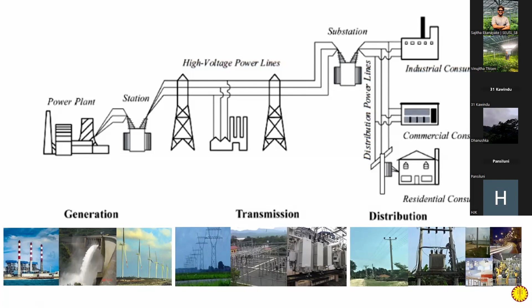In this power system, the reason you have system control is that from the generator, or in the power station, you have something called a synchronizing breaker - the circuit breaker connecting into the transmission network. From that synchronizing circuit breaker up to the 33 kV circuit breakers at the grid substation, everything is controlled by the system control center. In any country, in any AC power system, there should be some control center with the authority to control the circuit breakers and generation.